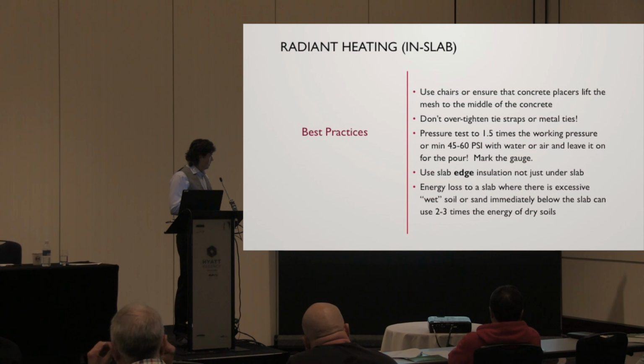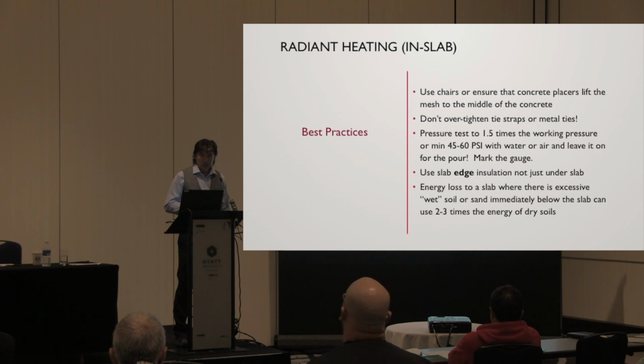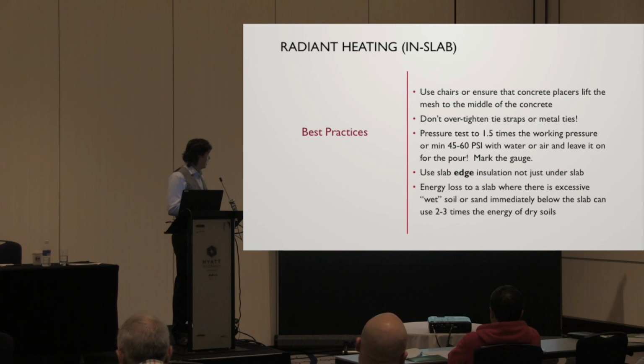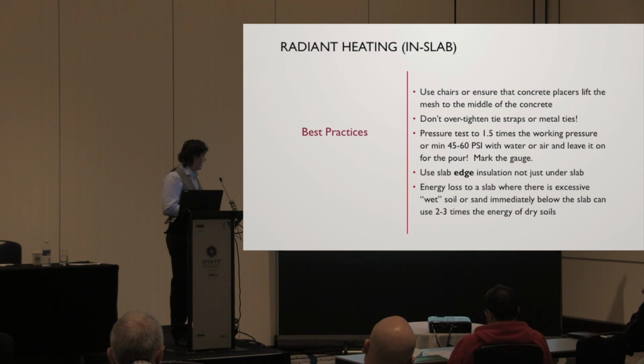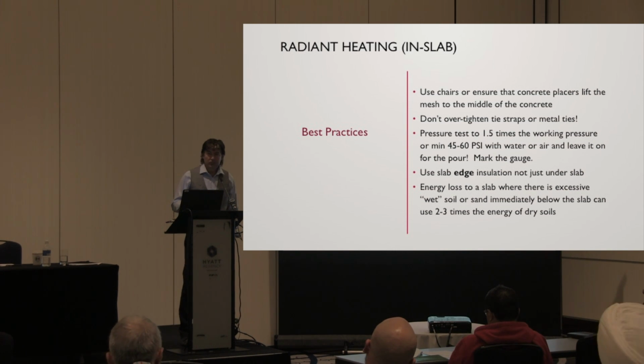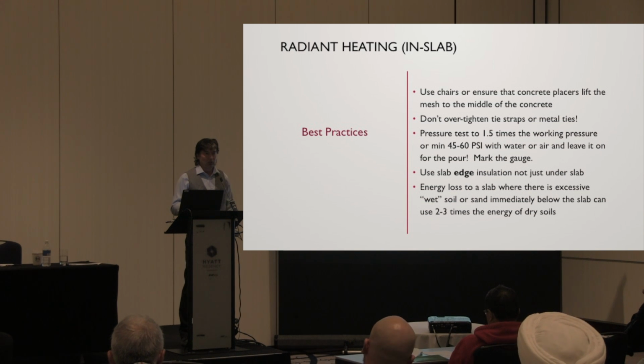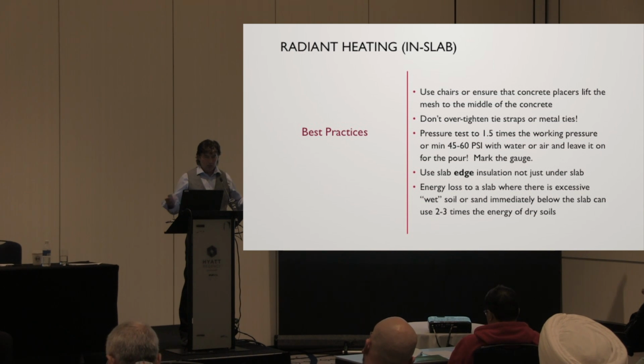Okay, use slab edge insulation. Who does that? Show of hands. Slab edge insulation. 2 guys. 3, 4, 5. Okay. We know that we have to use insulation below a heated slab. I'm assuming everybody's aware of that. If not, let's make it clear. The building code says you have to insulate below a heated slab. R12, it's really the discretion of the municipality or the building official, but you're going to wind up with either R10 or R12. Which is fine, and David will really dive into this subject when he talks about F280 and the nature of how to insulate basements and the calculation of it.